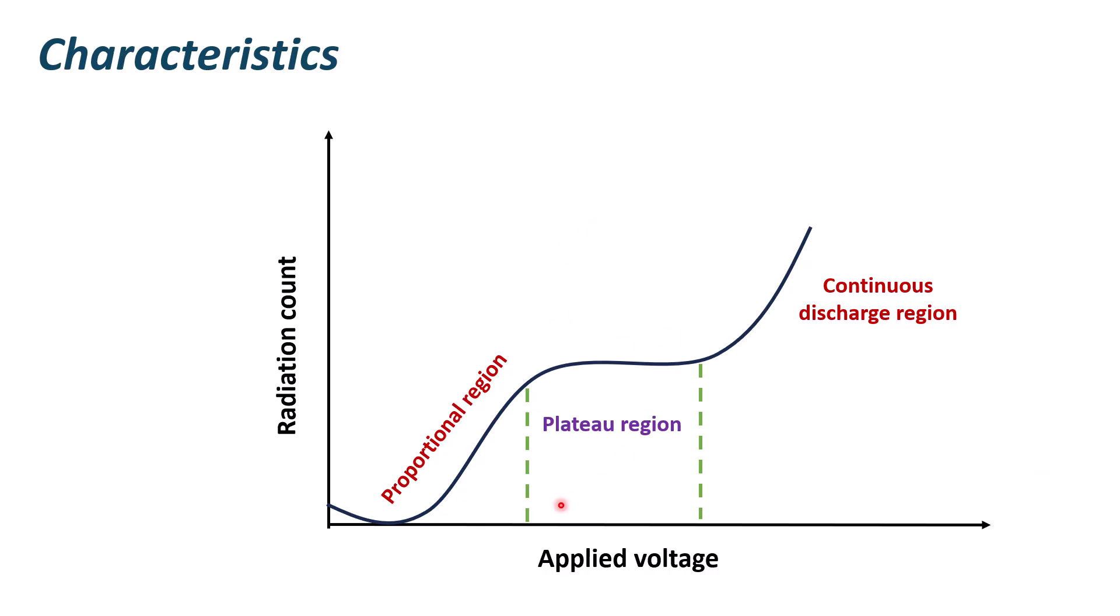Basically, if you want to work with the GM counter, applying voltage in between the plateau region is required. And therefore, in order to calculate optimal voltage of the GM counter, we need to see where that plateau region is started, where it ends. And if you take average of that two voltage values, you will get the optimal voltage of the GM counter.